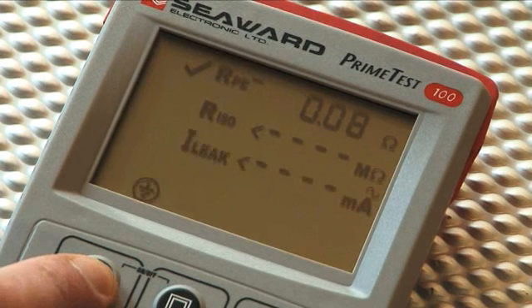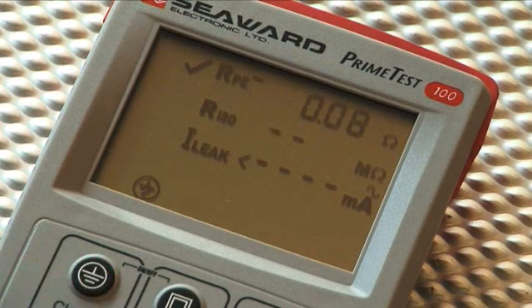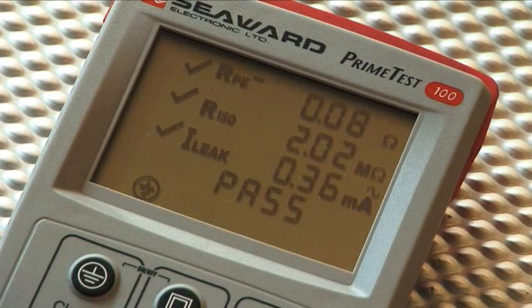The Class 1 key is pressed again to proceed with the Insulation Resistance test. The Primetest 100 will now measure the Reference Insulation Resistance value in the PAT checkbox and display this reading with the Tick Annunciator. It will then measure the leakage.